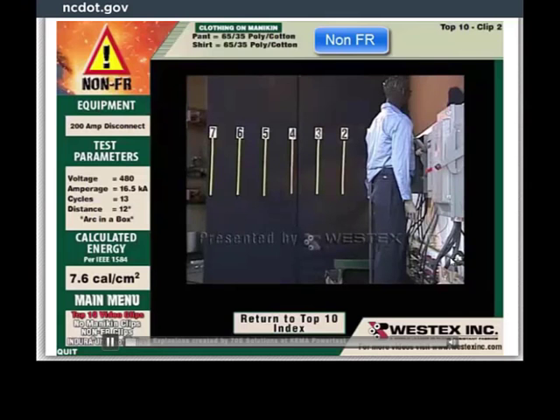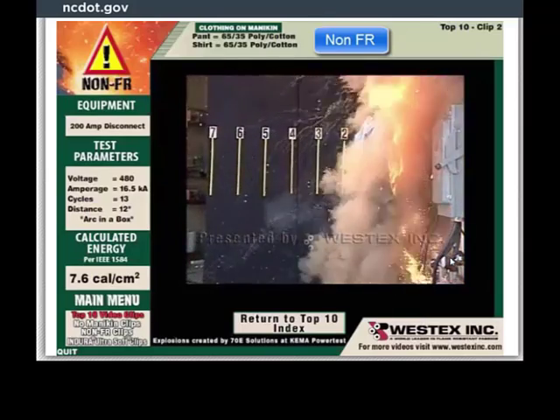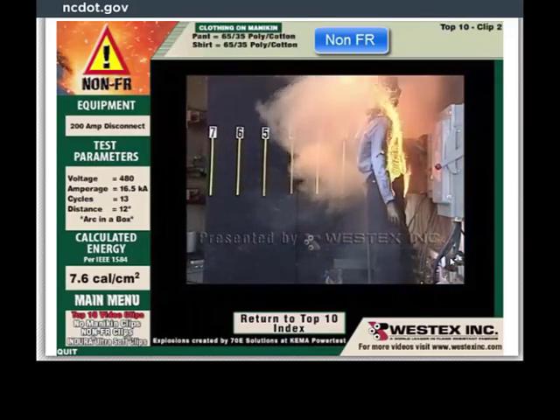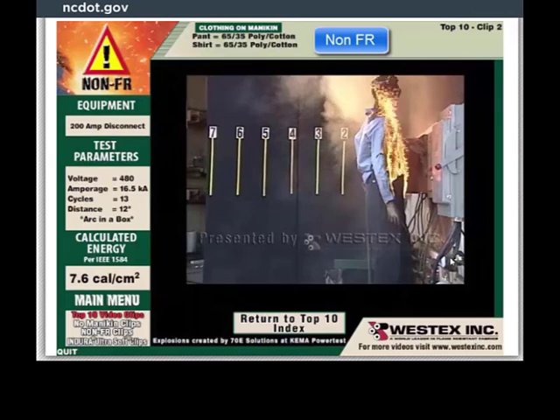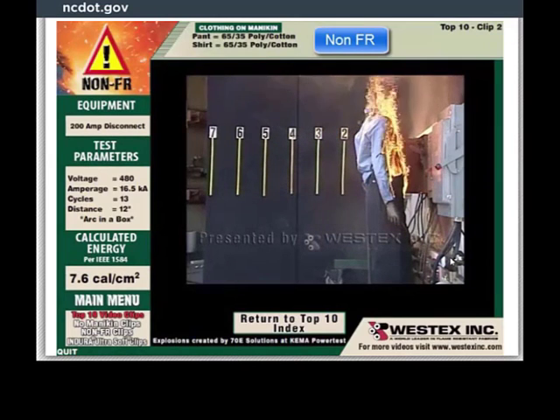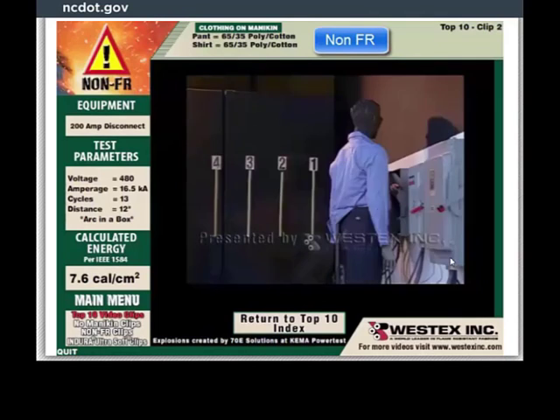Now the arc with a polyester cotton shirt and pants. The arc and the clothing is immediately on fire. And not just the shirt, but notice the pants as well, even though they would not have been predicted to ignite in this arc, they did. And the clothing will continue to burn, dramatically increasing the severity and the extent of the burn injury that would be suffered in this instance. You can see how rapidly as well the fire progresses to the back of the shirt, which would not have been injured in the original arc flash.